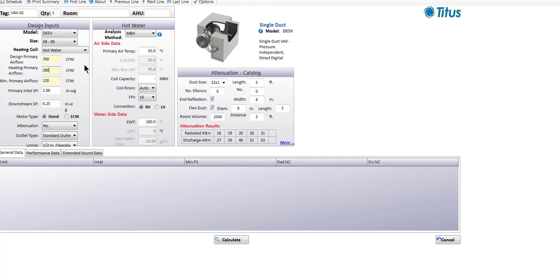That's by far the most efficient approach. Back in the old days with pneumatic controls, the box typically modulated from cooling design down to heating, which was very inefficient because it caused us to sub-cool the room before we had to heat it back up again — a huge waste of energy.